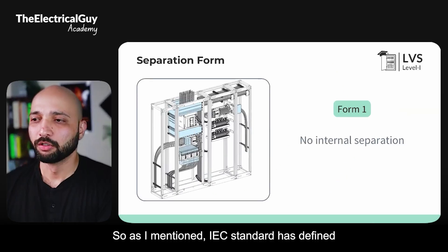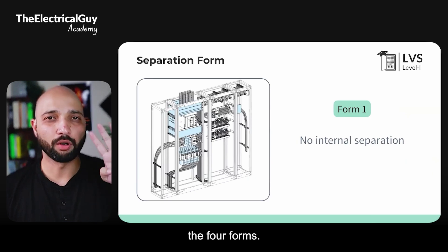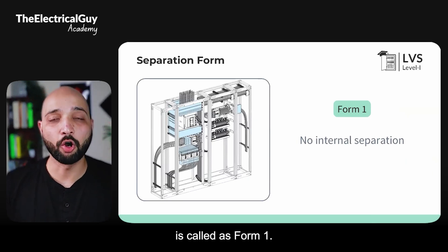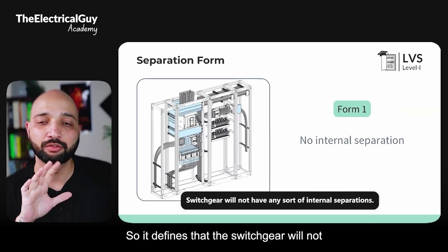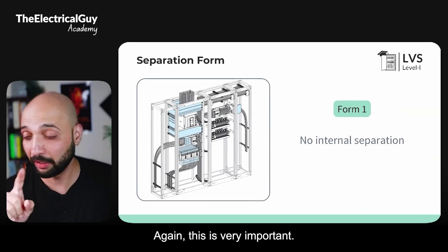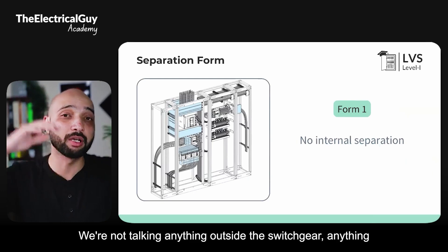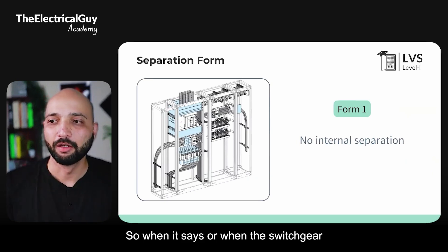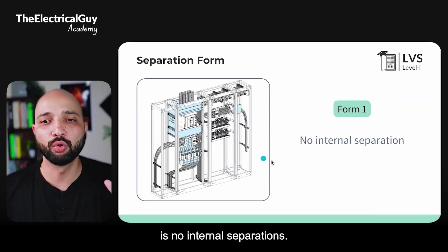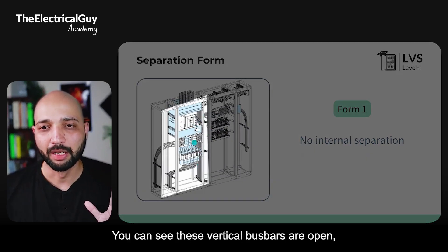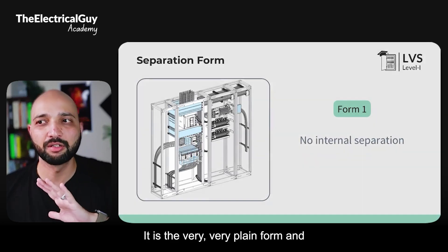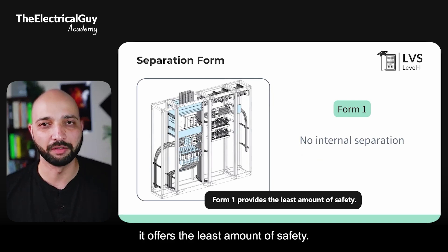Let us understand the four forms. Form 1 defines that the switchgear will have no internal separations — we are talking about separations within the switchgear, not outside the metal enclosure. The vertical busbars are open, the MCCBs are open, and there is no separation between any parts. It is the most basic form and offers the least amount of safety.